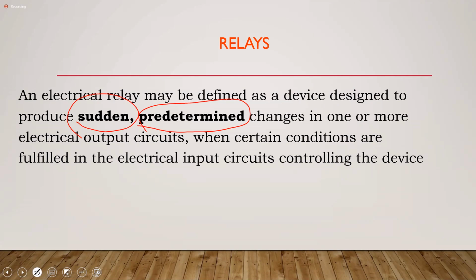So they are going to decide what will happen based on a particular input. So if the current, and we're going to talk a little about overcurrent relays, but if the current goes above a certain value, the relay knows that it must operate. Still yet, if it goes above a certain value, it knows that not only should it operate, but it should operate with a particular speed. So if the current is X times the setting current, then it's going to operate at this speed. If it is 10 times, then it's going to operate maybe faster. If it's 15 times, it's still going to operate even faster. Right? So these are the predetermined changes that the relay will make. Are we clear? All right.